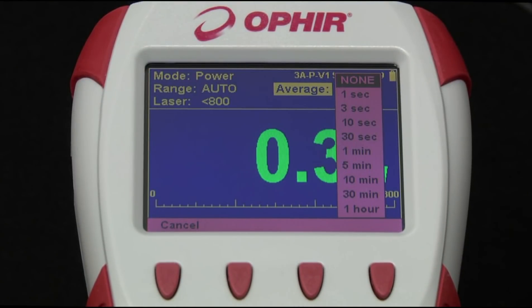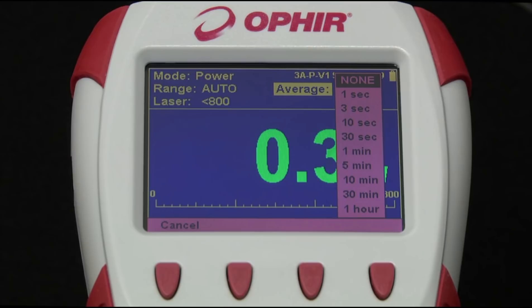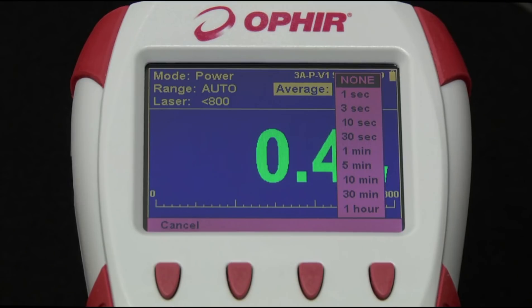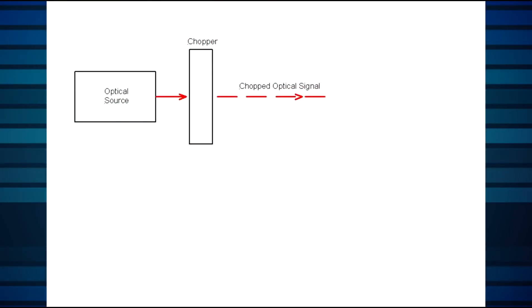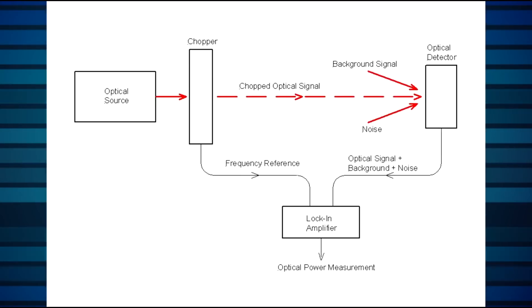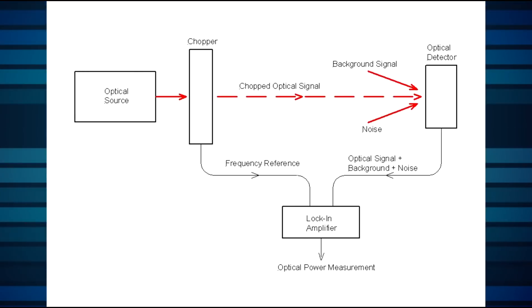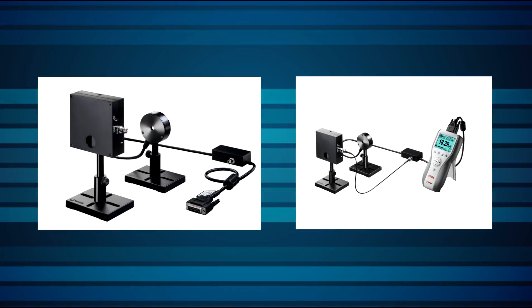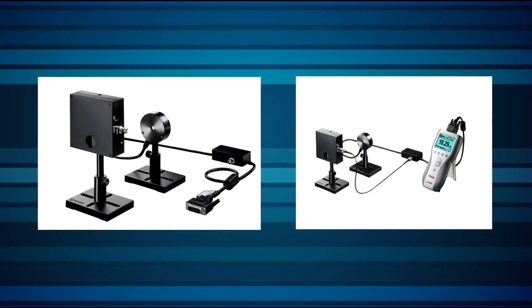For dealing with noise, the meter's average function displays the running average of the power reading over a selected time period instead of the actual real-time reading. This can help smooth out jumpiness in readings of an unstable beam by averaging out random noise. Measuring below the noise floor is sometimes made possible by using a lock-in amplifier. The beam is modulated at a specific frequency by a chopper, and the lock-in amplifier essentially ignores any signal not modulated at that specific frequency. Noise can be reduced with this technique by several orders of magnitude. Ophir has a family of sensors called the RM9 family that uses this method to measure powers as low as the femtowatt range.